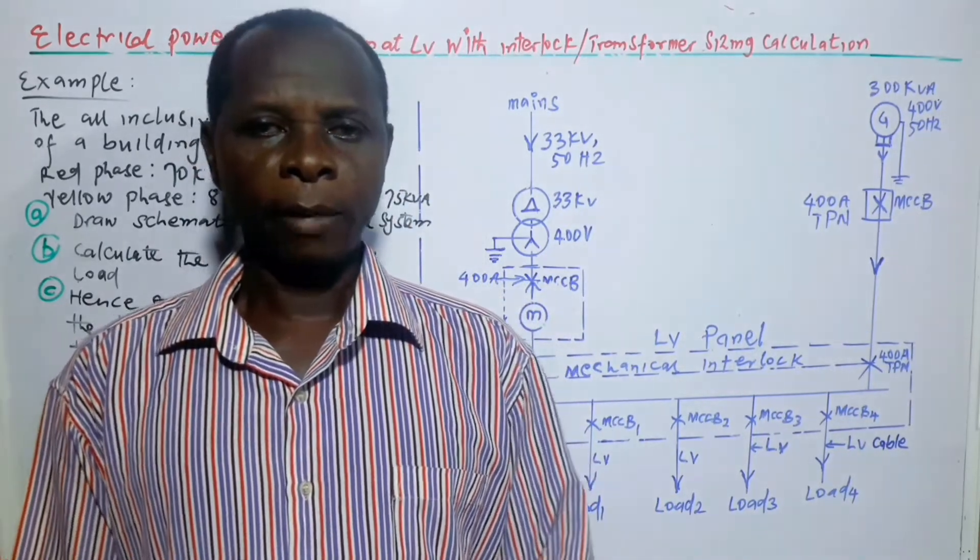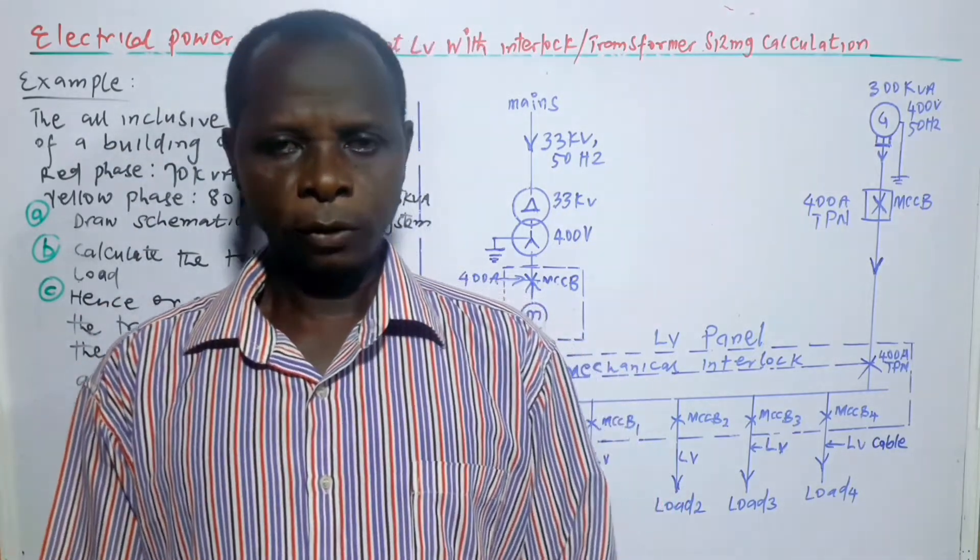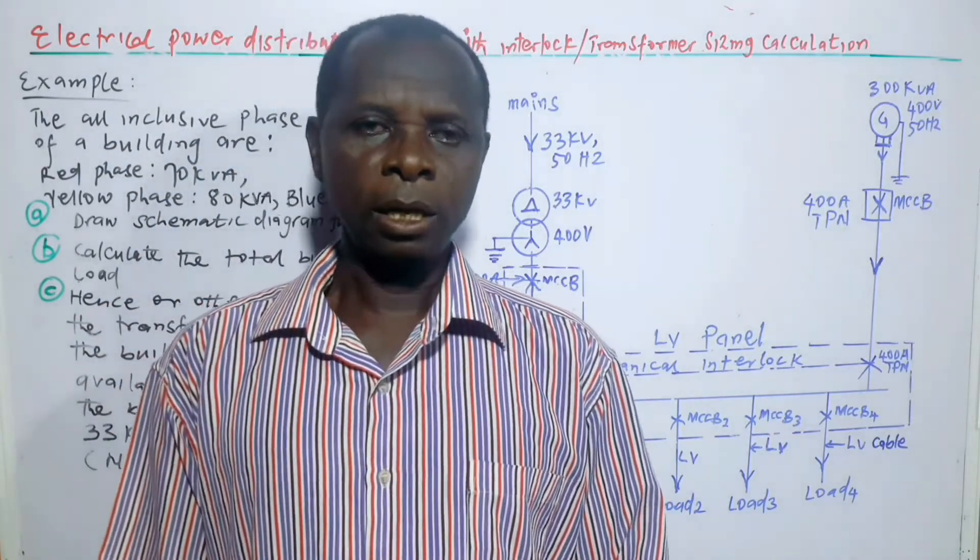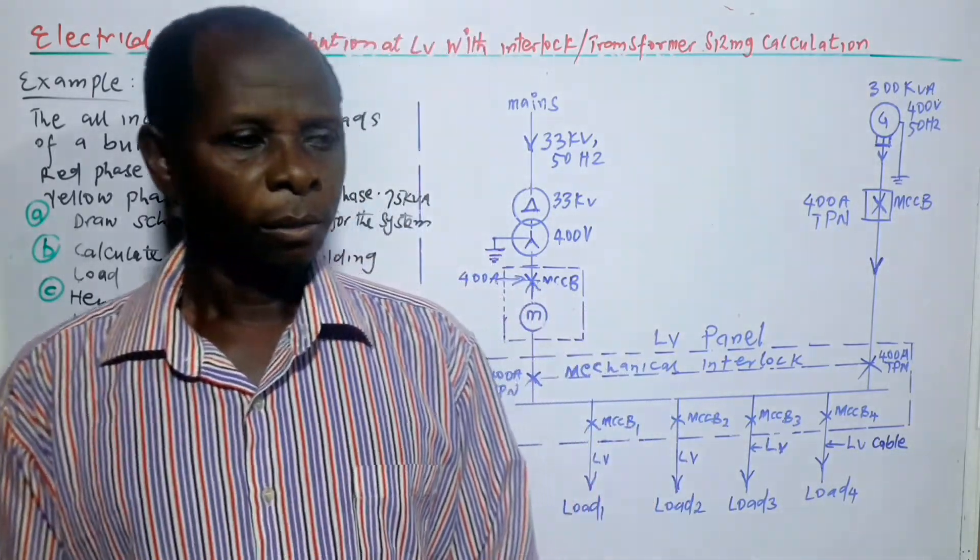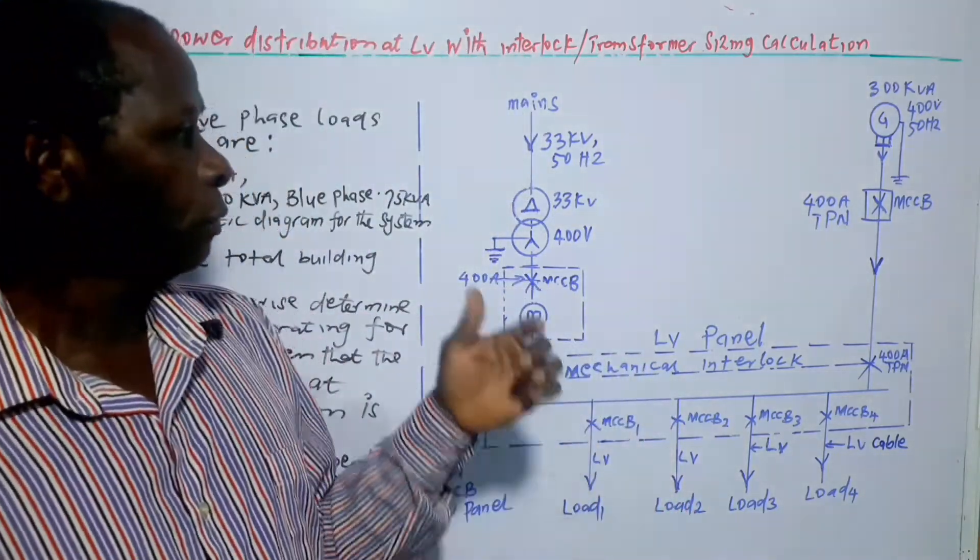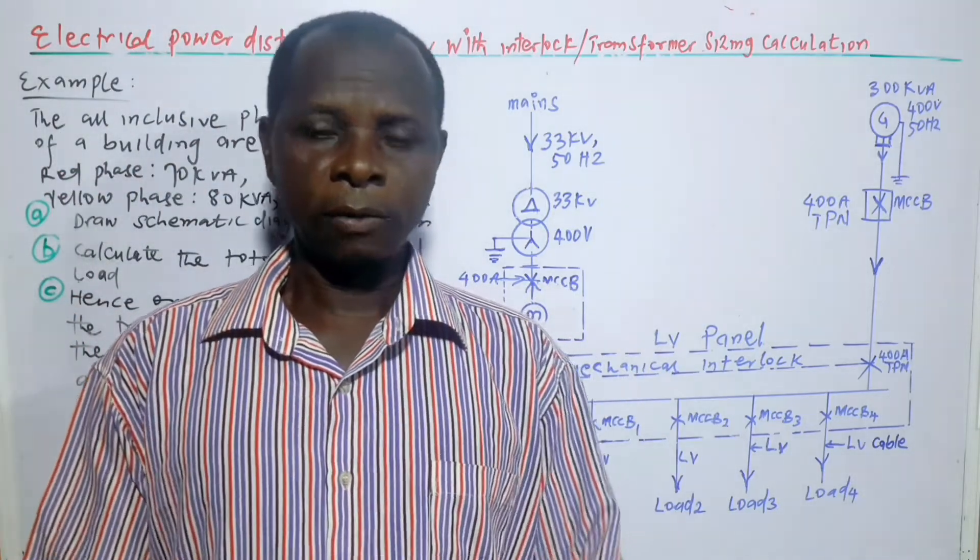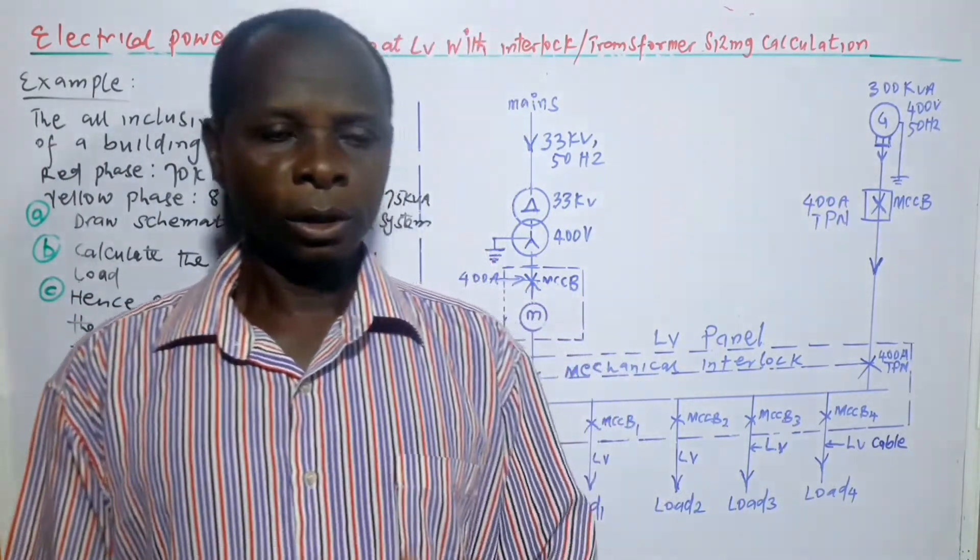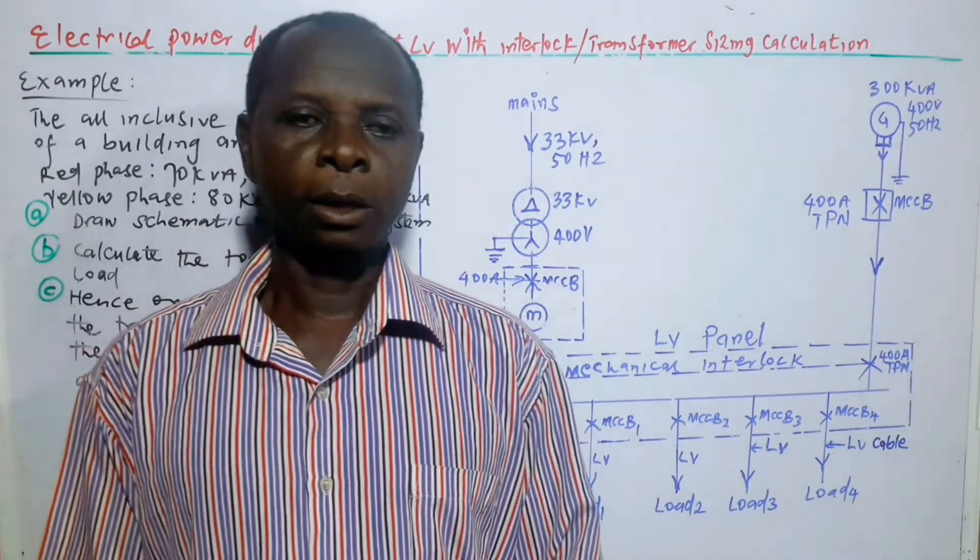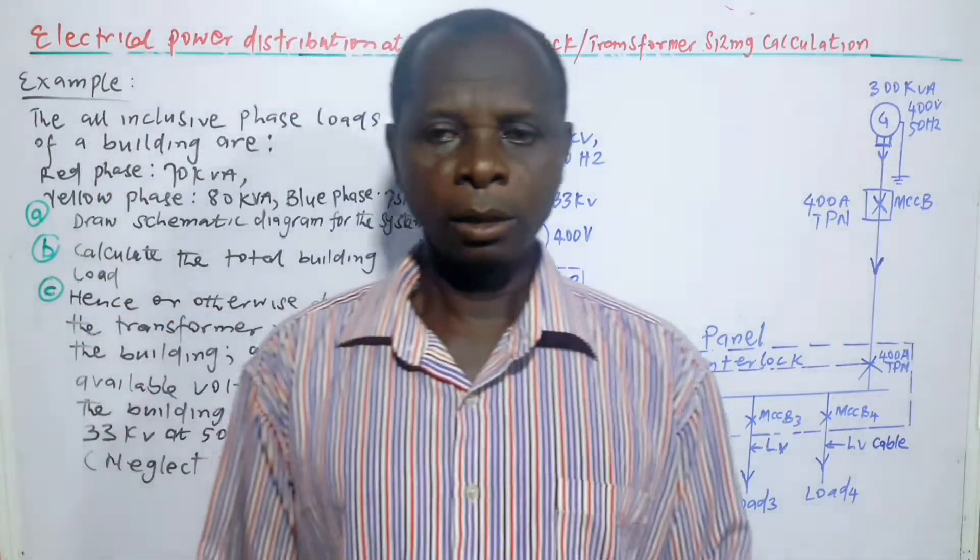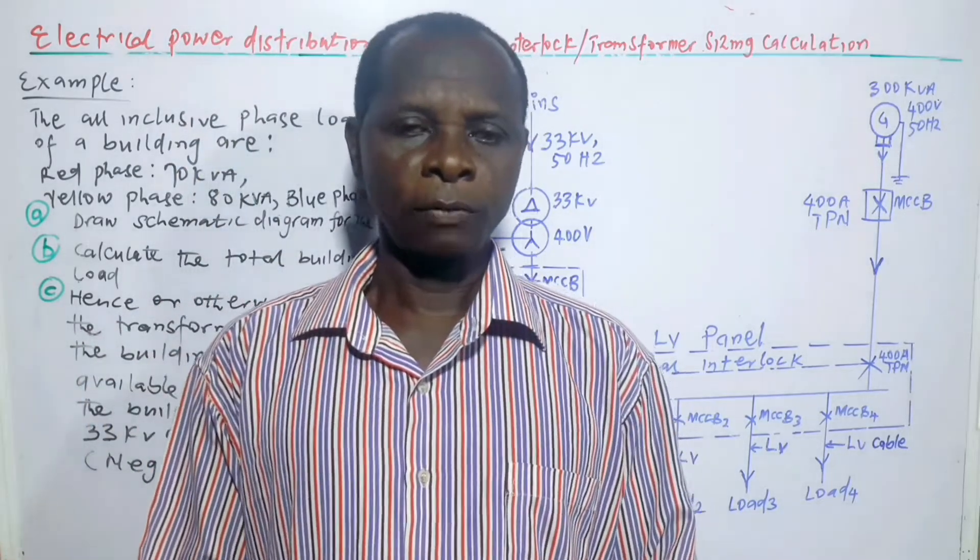In some of my previous videos, power distributions were done at medium voltages, mainly 11 kV or 33 kV. But in this situation, even the supply transformer which has 33 kV, the 33 kV is stepped down to 400 volts for the purpose of distribution at low voltage, as indicated by the topic of this video.